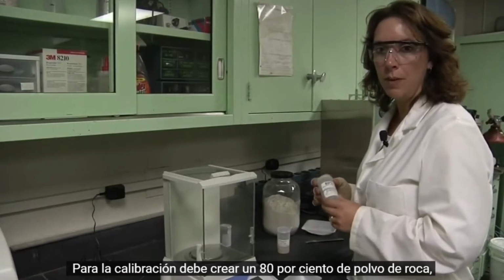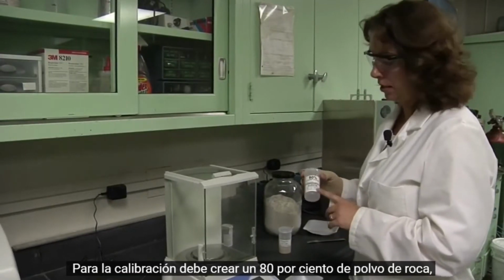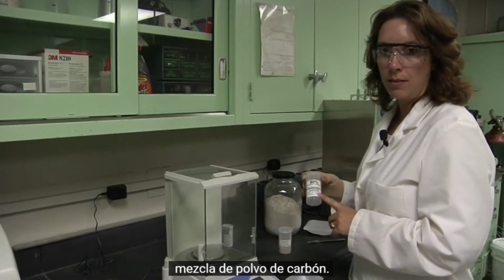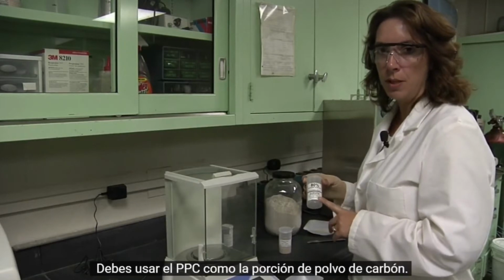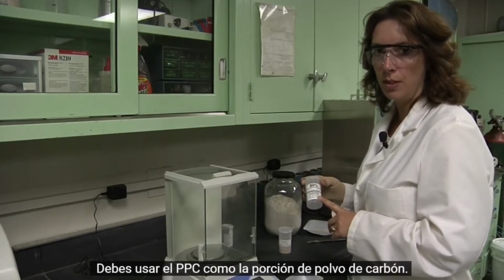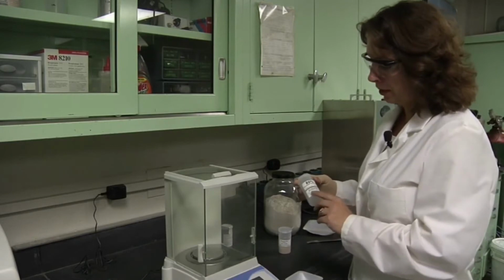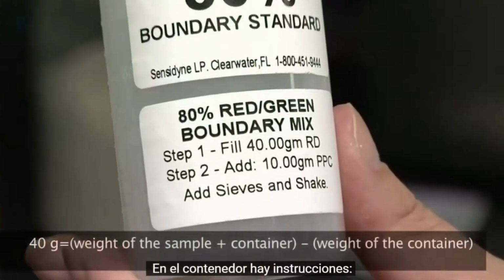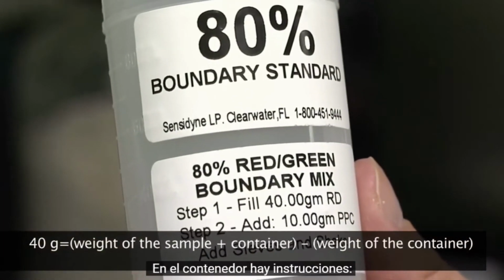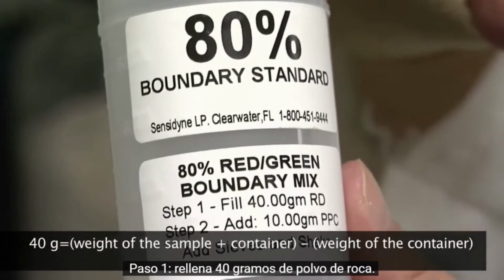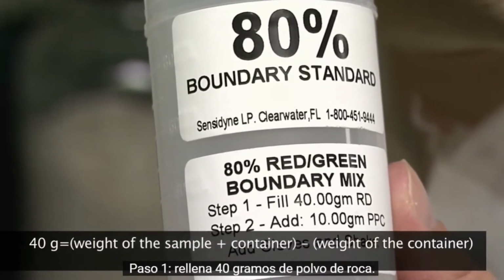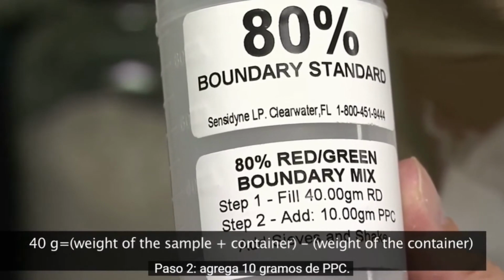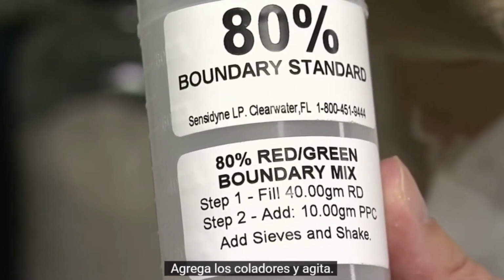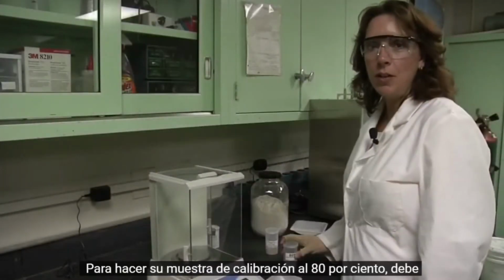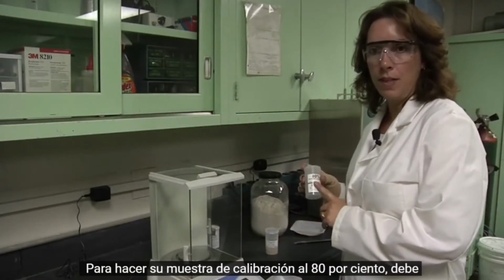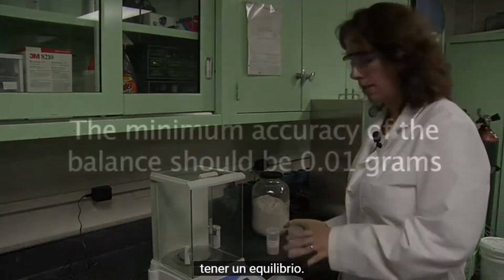For calibration, you must create an 80% rock dust, coal dust mixture. You must use the PPC as the coal dust portion unless otherwise directed. On the container, there are directions. Step 1, fill 40 grams of rock dust. Step 2, add 10 grams PPC. Add sieves and shake. To make your 80% calibration sample, you must have a balance.